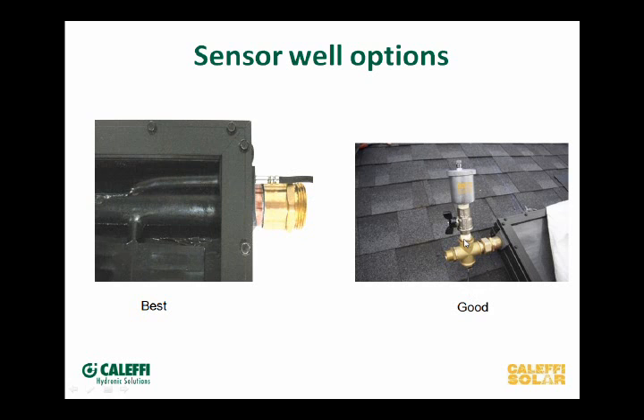We also started putting sensor wells on our collectors — a piece of copper tubing brazed right onto the header pipe that our sensor fits snugly into, inside the collector box. So now we're under the glass, against the tube that has the fluid in it. That's probably even nicer than having it on the outside, and it cleans up the look of the collector. So the cross fitting could actually be a T or an elbow depending on whether you still want the vent up there.